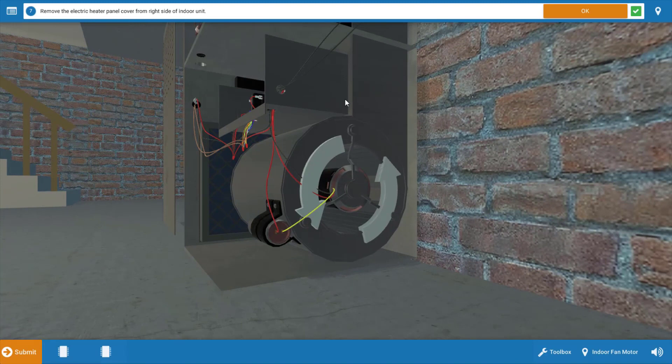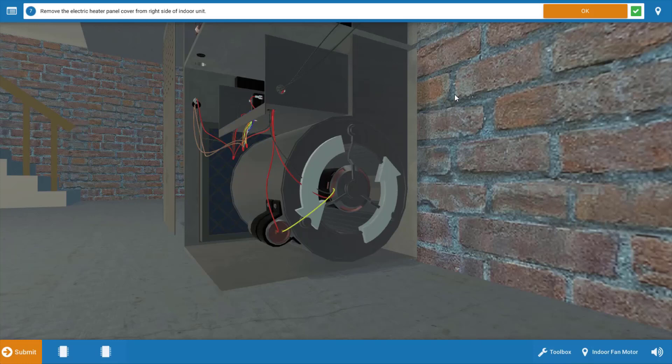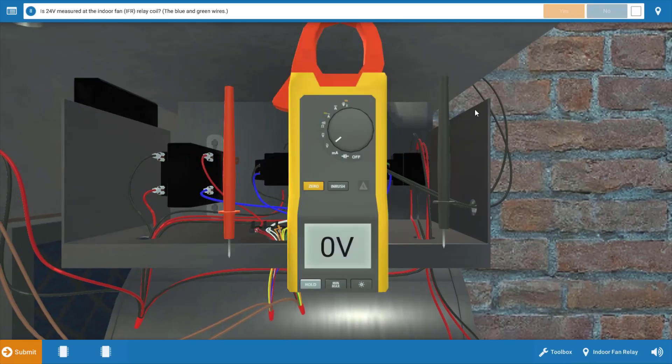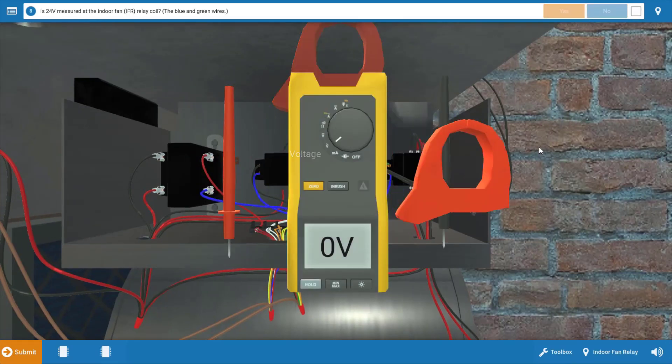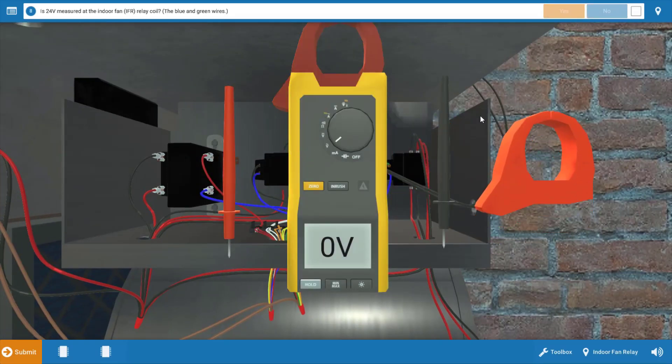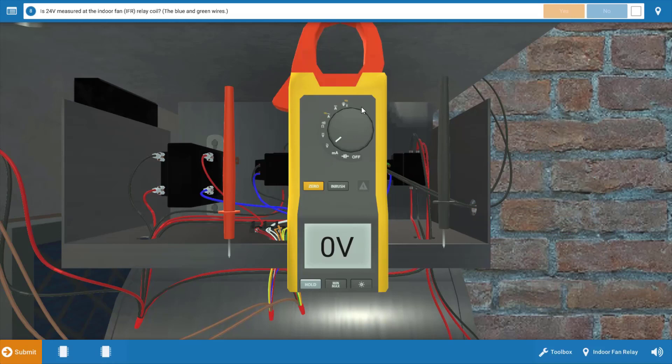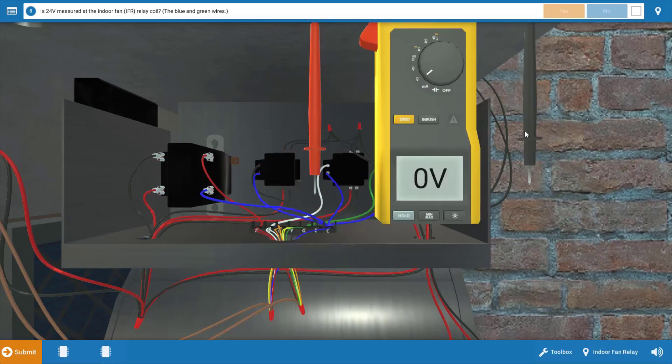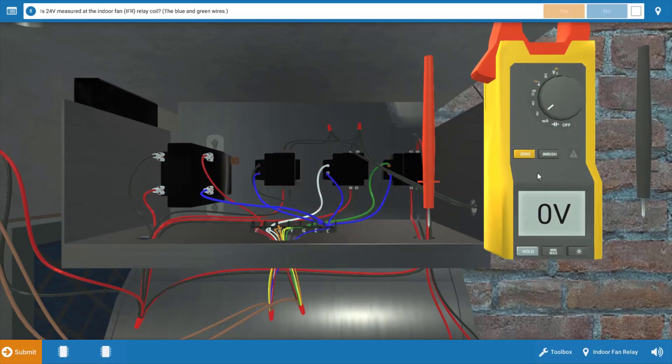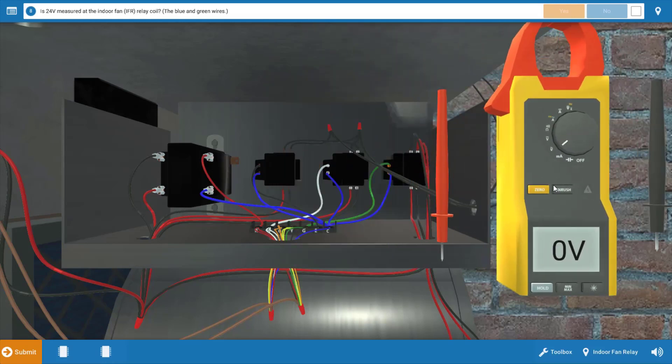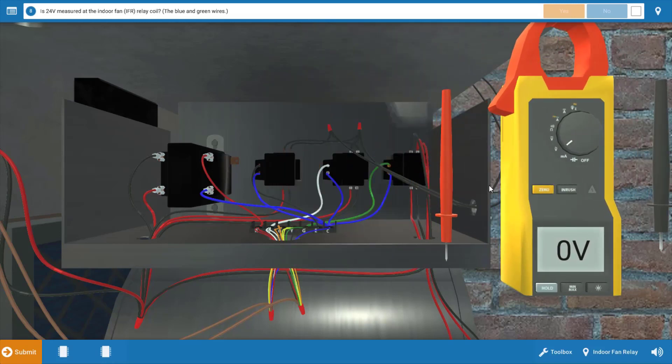Before we do that, we want to see if the electric heaters are running as well. So you can remove the panel from the heater, which we've done, and we can click OK. Our next step is to figure out what components could be possibly causing the indoor fan motor to not operate.